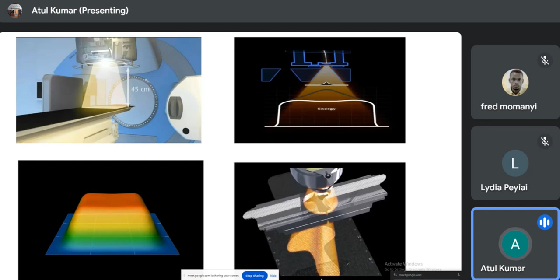If you have this flattened beam here, after it passes through the wedge, this is a very thick end on one side and thin end on the other side. So the thick end interacts and blocks most of the radiation. So you get lesser dose on one side and higher dose on the other side, and you can modify your dose, and you can have a dose gradient which you can use to shape your isodoses. This is physical and non-physical wedge. There are different types of wedges. If you don't know, we can discuss it in the QA.